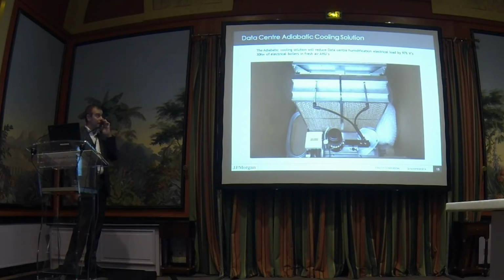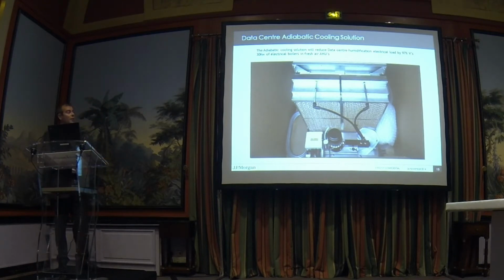Well, hang on a minute, I'll take out the boilers, steam boilers, and I'll put in these adiabatics. I'll get cooling and I'll get humidity into the space. Just the price of pumping some water into it. The expensive part's the RO plant, but it does double the consumption. You process 20 litres of water, you've got 40 litres getting thrown to waste. So we're going to put a tank in outside that will collect that water for the toilet flushing and carrying on.